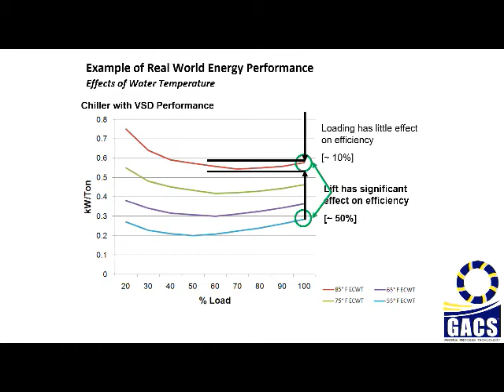Lower cooling tower temperature is possible by designing the cooling towers on the right wet bulb temperature or the right ambient temperature of that particular location, not on thumb rule based calculations. Now coming to the building management system, we always know that a building management system operates the AHUs of a building. It regulates two-way valves, three-way valves, pumps, chillers and all. One can centrally operate the building.